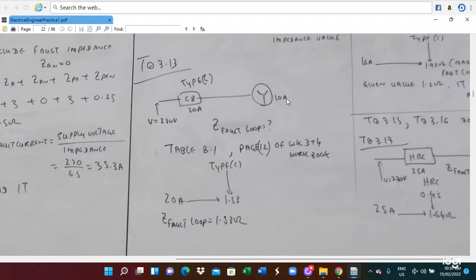So this problem is a supply transformer. Supply voltage 230 volt and circuit breaker, the rating is 20 ampere and also the socket outlet is 10 ampere. We have to calculate the fault loop impedance. So in this case, how to calculate this fault loop impedance? In this case, this supply circuit breaker is type C. Type C circuit breaker. So we have to refer to the AS 3000 table 8.1. So type C circuit breaker, and then the current is 20 ampere. So then this fault loop impedance is 1.530 ohm. So this is the way we can find out the fault loop impedance.